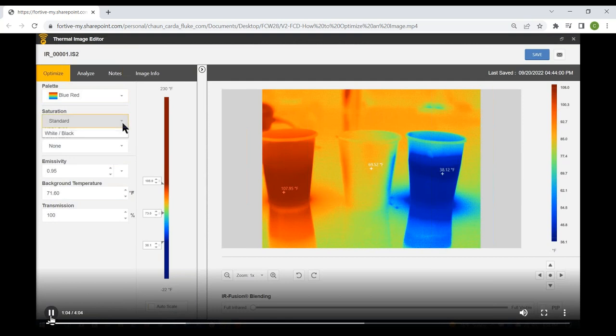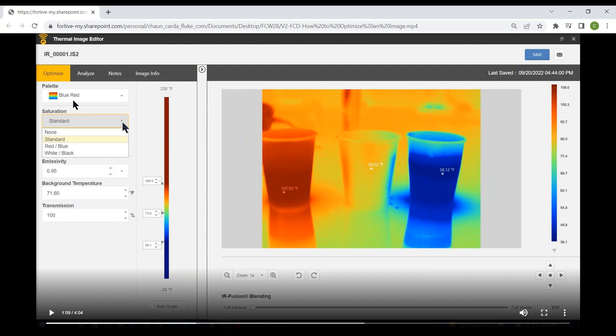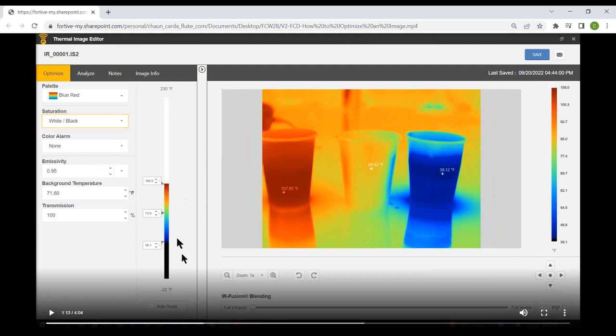We reset everything and move on to the Saturation option. Here we've got four options: None, Standard, Red-Blue, and White-Black. Saturation is simply what color things appear that are out of range. If you select Standard, it uses the palette to define the out-of-range colors — so on the Blue-Red palette, everything hotter than the hottest point is dark burgundy and everything colder than the coldest point is dark blue. Switching to White-Black means everything hotter than the hottest point shows white and everything colder than the coldest point shows black.